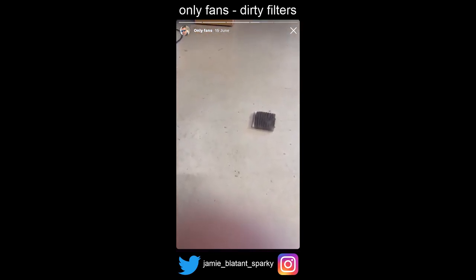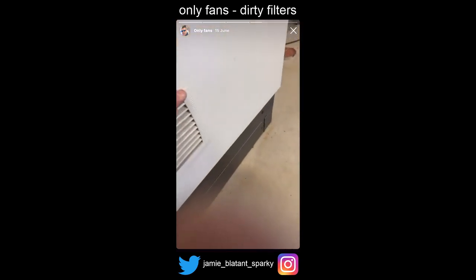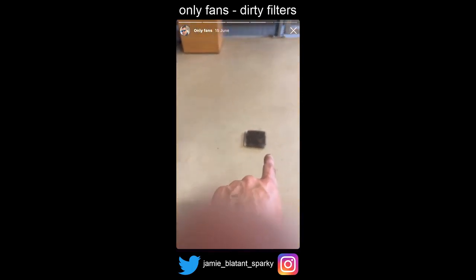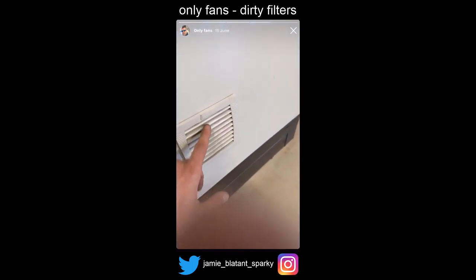...and I throw them away, because that is microscopically fine dust that's filled the filter over a number of months or even years. This is not a dusty environment, and that fan is now absolutely blasting air through, keeping the electronics cold. It wouldn't matter if that little bit of fine dust had gone in there — the electronics probably survived. Regular occurrence. The only thing in the panel likely to raise the load is this fan.